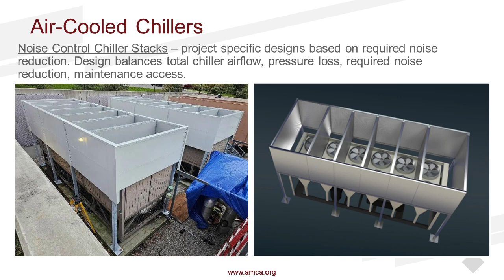The problem with this particular project was they have a nice equipment yard here, poured concrete, but there were condos and it was making noise and had problems at the property line. So there was noise up and over this wall. You see the wall's not much taller than these units. Well, they were with the stack. It was like a 3-foot difference. And then there were also condos on this side where I am that actually have balconies over. This was all new construction around this area.